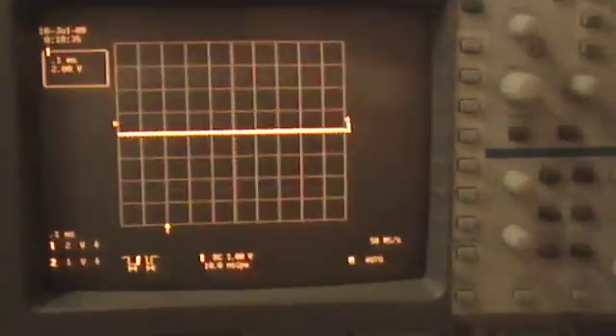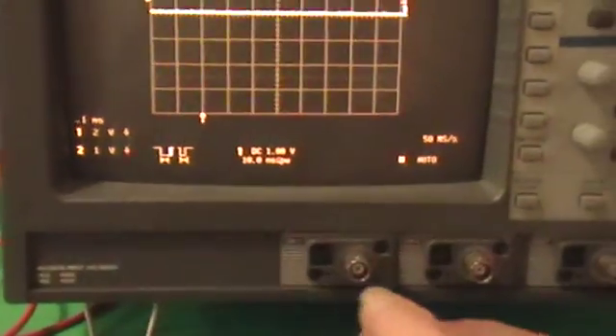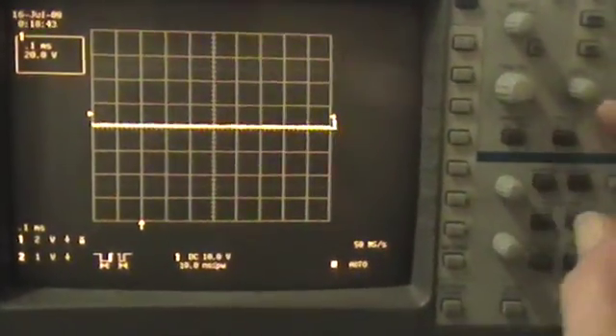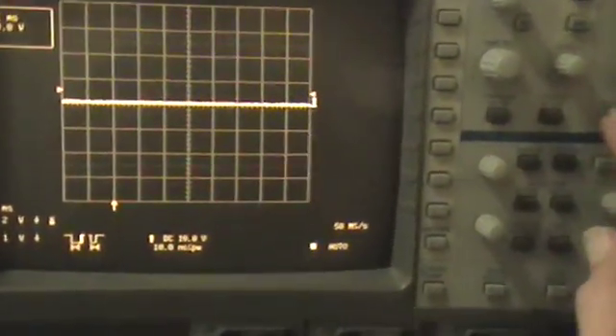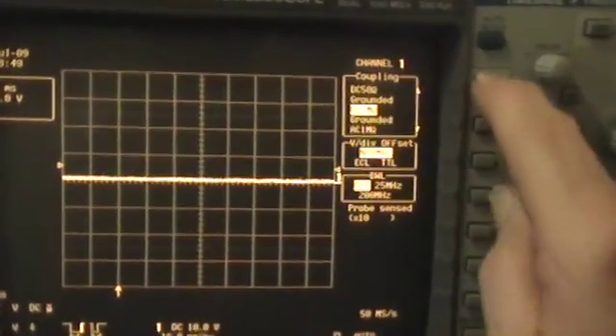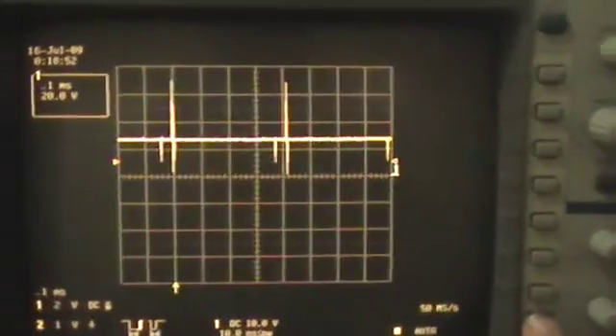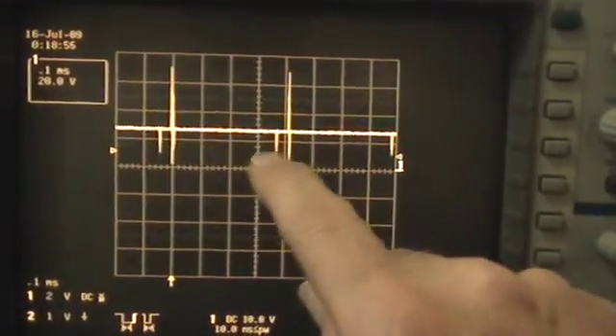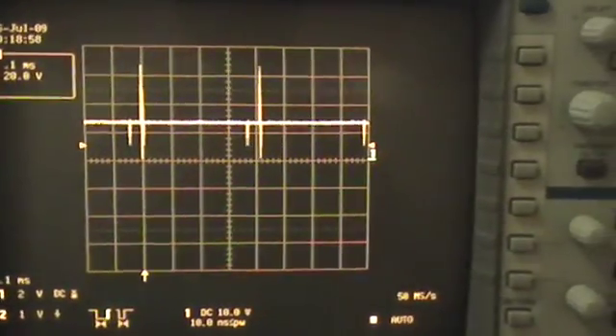And I'm just going to plug it in like that. And I've got that channel grounded now, so let's see here, coupling, and DC one megaohm. Okay, so now you can see the spikes there, but there's no drop of the voltage in between, right?